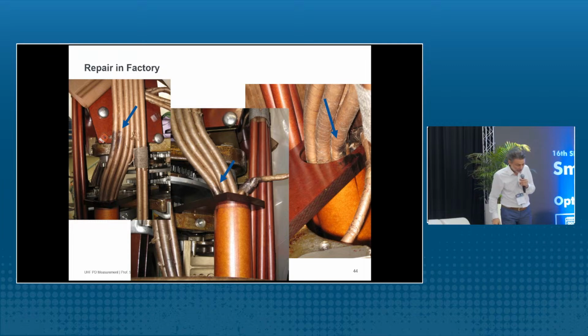Yeah, and the origin was in the region where the tap changer was installed, and you know the region of the tap changer can easily be accessible. Yeah, if it's within the winding, it's of course difficult, but in the tap changer region you can do some repairs. So the transformer was brought back to factory and opened, and here you could see these dark spots on the tapping leads, and you know, if this PD would have been continued, then you would have a failure here, a breakdown, and a breakdown on the tapping leads normally means full loss of the transformer. So, and repair is quite easy, because you just have to exchange the paper here, you have to dry the active part again, put it back into the tank and refill the oil, and yeah, it's still operating, the transformer.